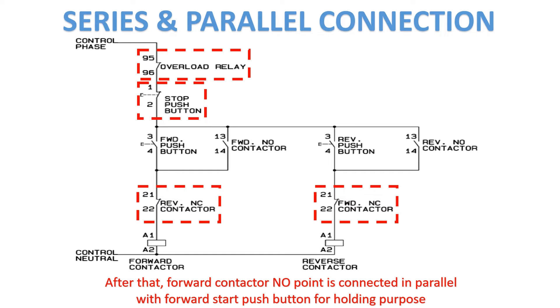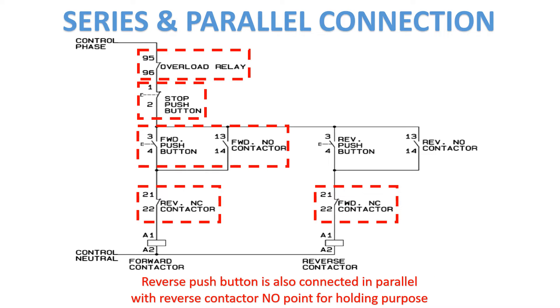The forward contactor NO point is connected in parallel with the forward start push button for holding purpose. Similarly, the reverse push button is also connected in parallel with the reverse contactor NO point for holding purpose.